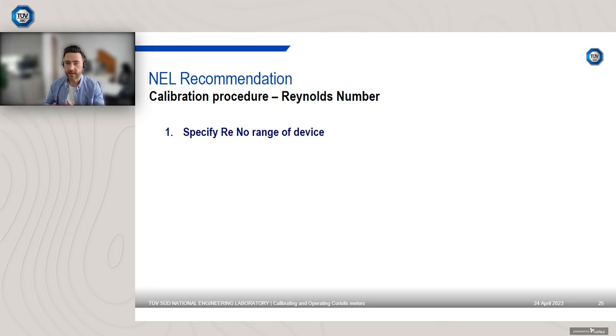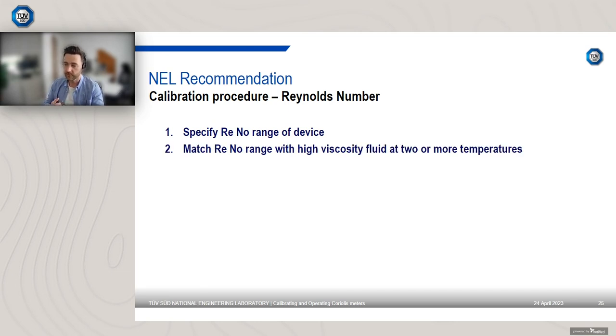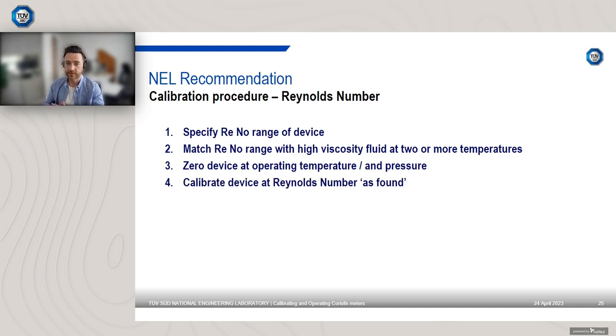We specify the Reynolds number range of the device. So this involves us speaking with the client to ascertain what the viscosity, what the geometry of the device is, geometry of the pipeline, what the fluid viscosity, density, and flow range is, and we can look at the Reynolds number range. We'll then try and match that Reynolds number range for high viscosity fluid at least 2 or more viscosities / temperatures. We'll zero the device at operating temperature and pressure if required.